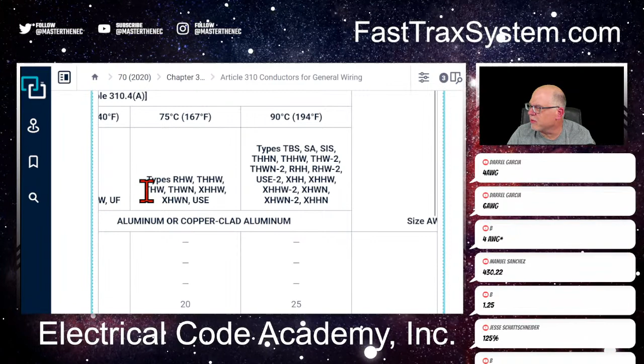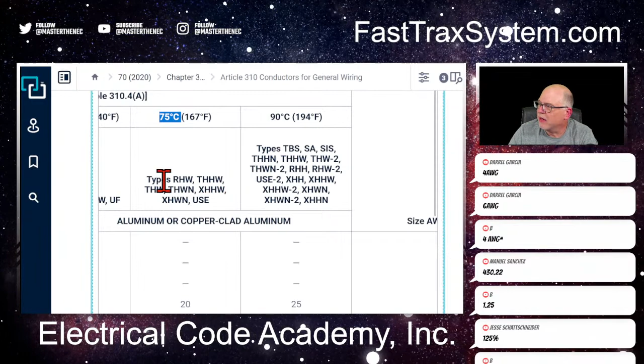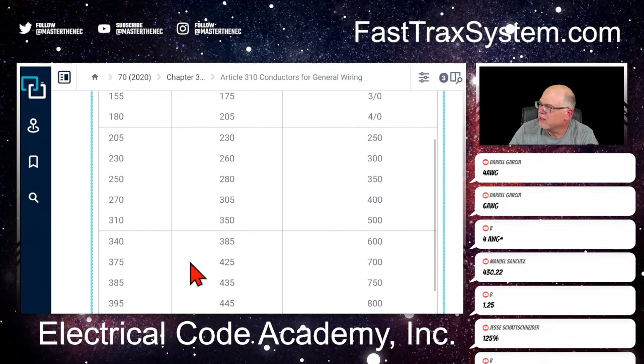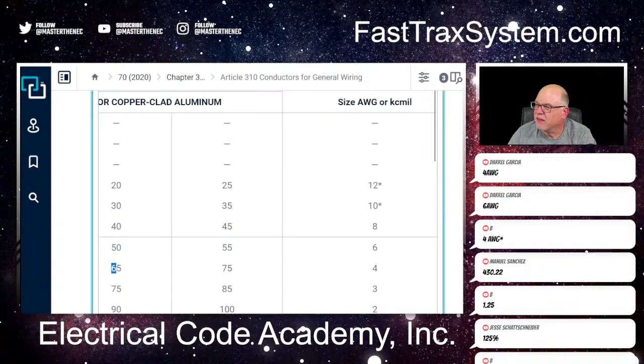Now, the first thing somebody's going to say to me is, what about the small conductor rules? Well, there are allowances under 110.14 that say if it's a motor, then the terminals are going to be 75 degrees C, and that's the case for most motors. So you're going to be in the 75, and you get to ignore that 60 degree if it's 100 amps or less. This is a motor we're talking about. THW, let's see what we got. I need one that's going to handle 55 amps. Looks like it's going to be a number 4. That would be the answer. So there you go: 430.248 by virtue of 430.22, and ultimately we end up in 310.16.